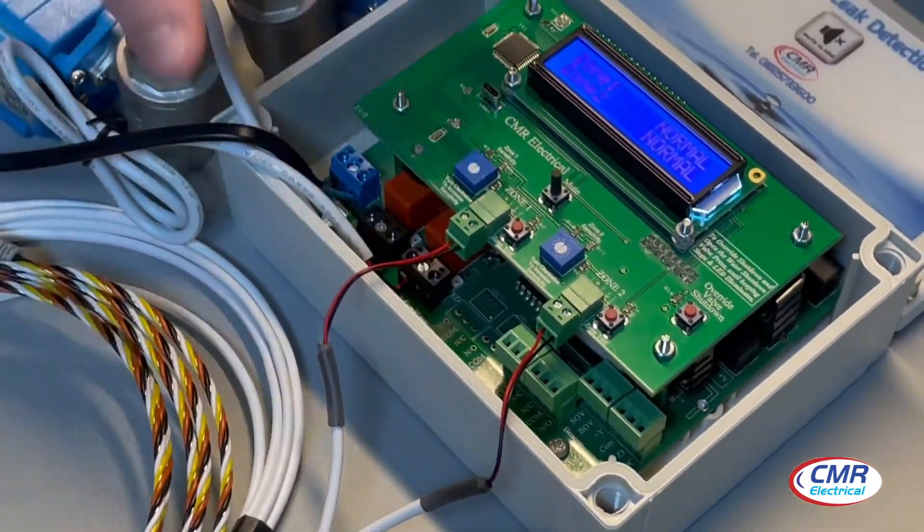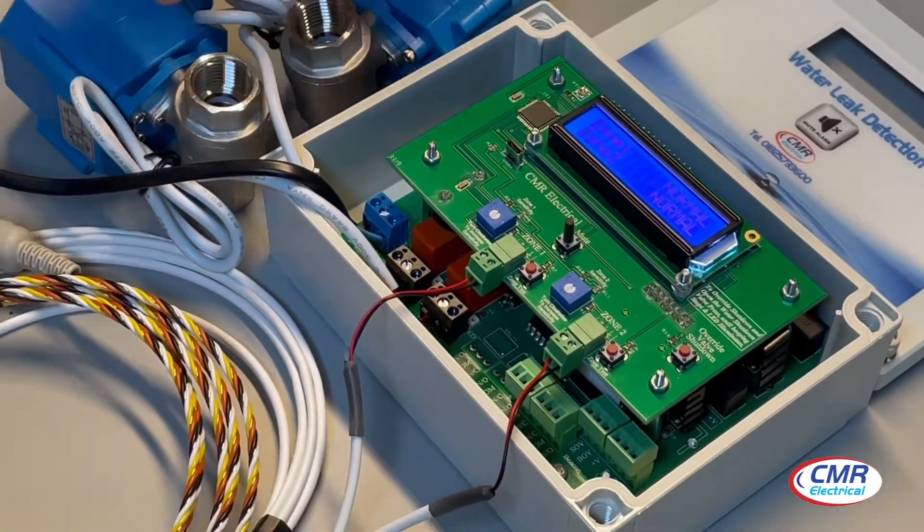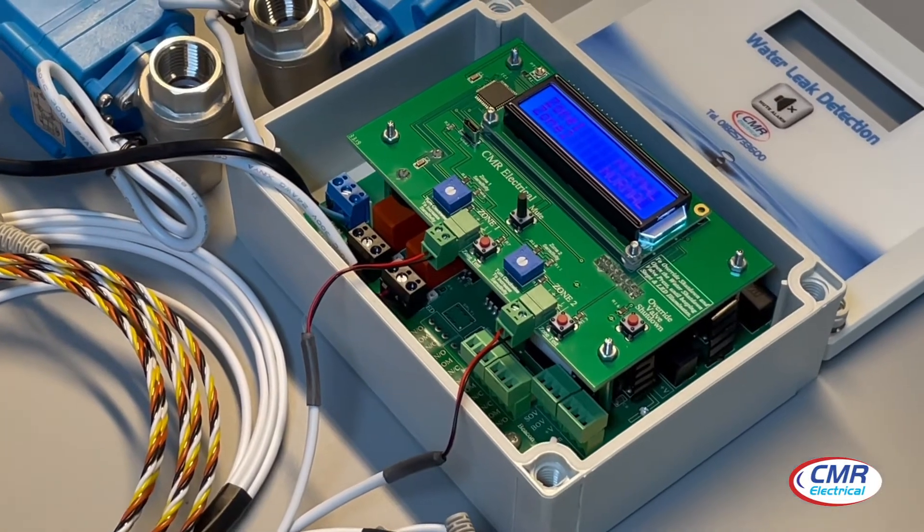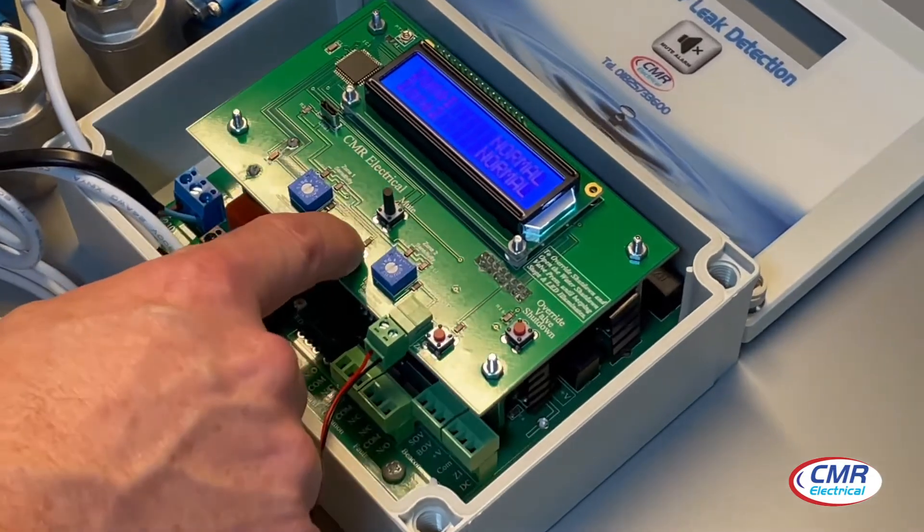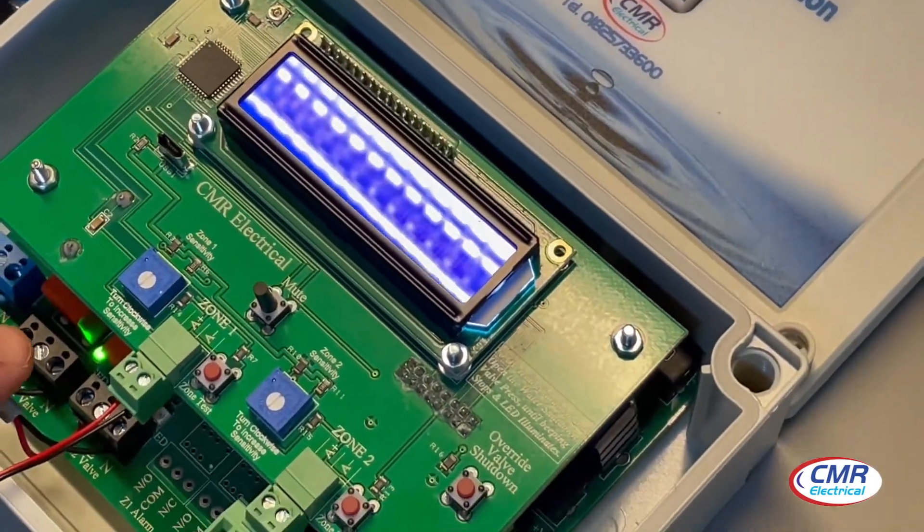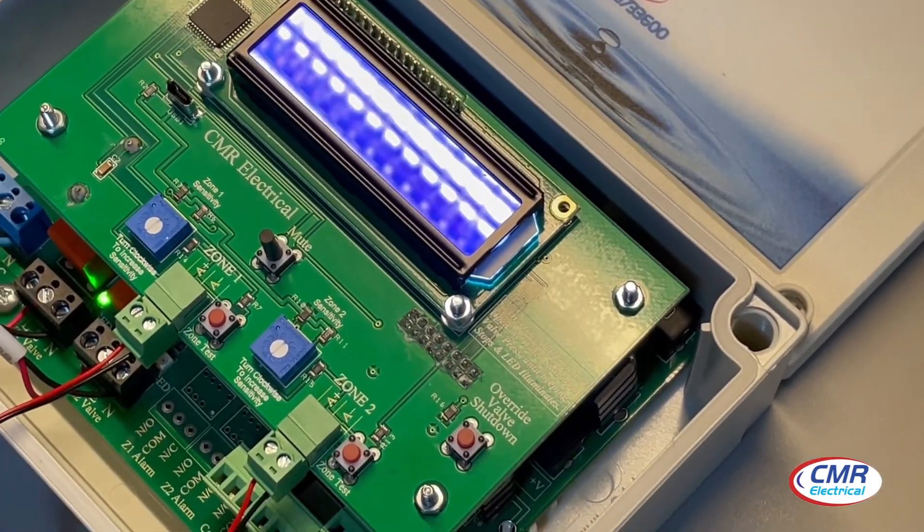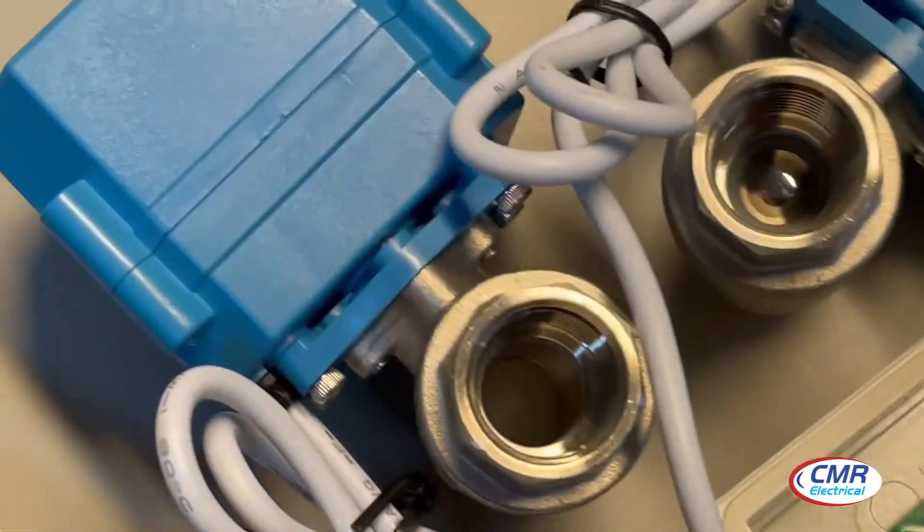Just to show the operation of the valves and how the valve works, I'll put zone 1 into alarm and show you how the valve turns on and off. Put zone 1 into alarm, a little LED comes on, and as you can see, the valve is starting to close.